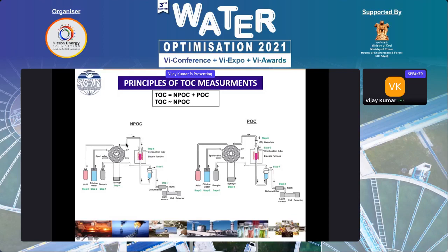In case the sample contains POC, normally POCs are not there, but if it is there, then you have a purge trap system. When you are sparging out the CO2 of IC, you remove the IC CO2 and the balance POC is injected here. That is how we measure TOC.